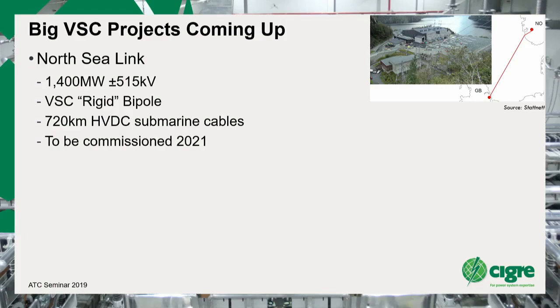Big VSC projects coming up: there's the 1400 megawatt link between Norway and Great Britain. It will be the longest cable - 720 kilometres long. Interestingly, it uses something called a rigid bipole. Very quickly, a rigid bipole is where you get away with just two cables. You don't have an earth return, so if you get a cable fault, that's it, you're out. But if you have a fault in the converter, one of the poles can switch over to the healthy pole. So it's kind of halfway between a full bipole and a monopole.